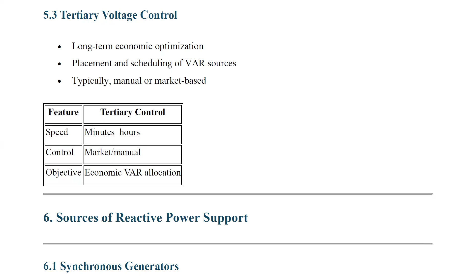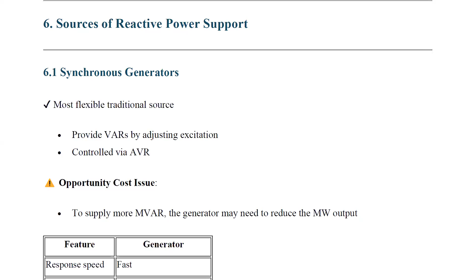Next, sources of reactive power supply. For example, the synchronous generator, a more flexible traditional source. It provides VAR compensation by adjusting the excitation, over-excitation and sometimes under-excitation, controlled via the AVRs, automatic voltage regulators. What is the main issue here? Opportunity cost. To supply more reactive power, that is VAR, the generator may need to reduce the megawatt output. But we need to balance the load also. That thing we also need to take into account.